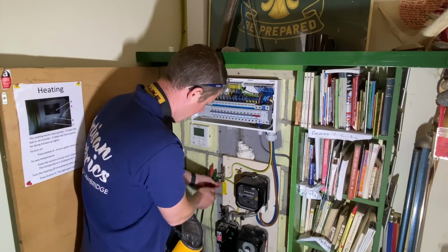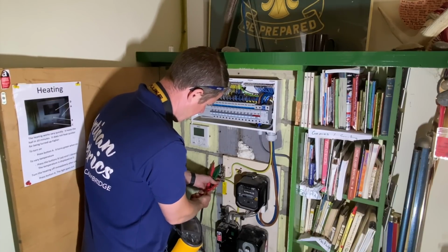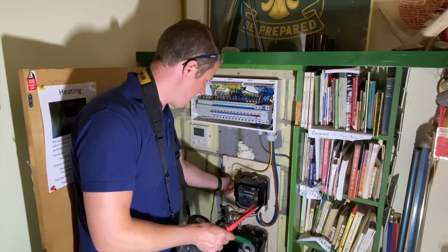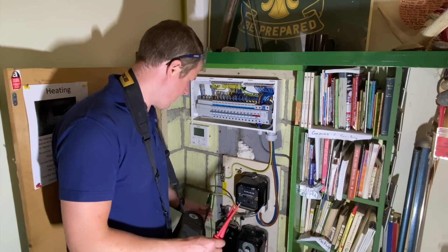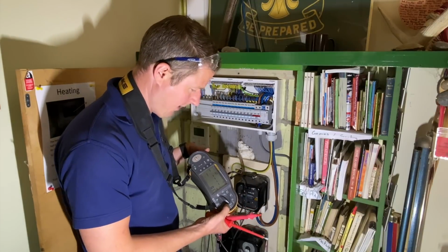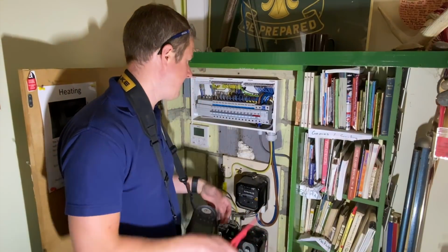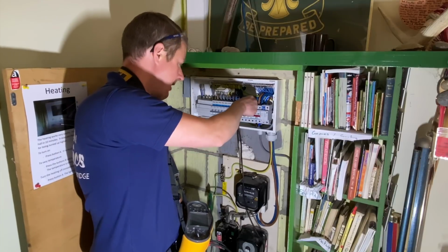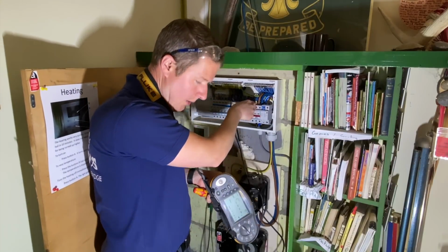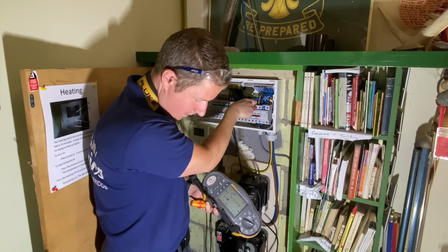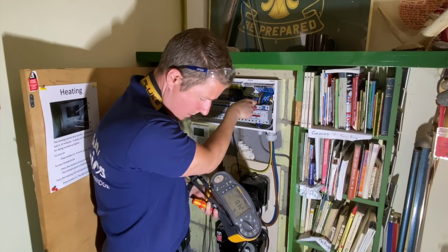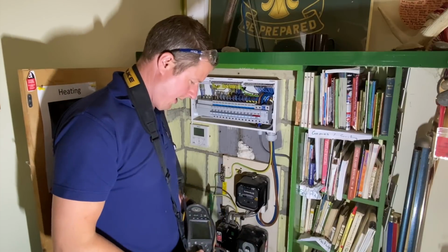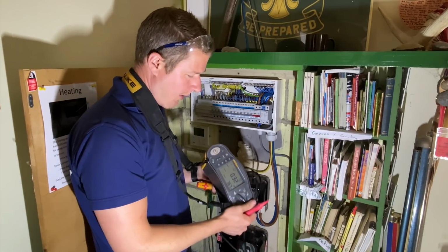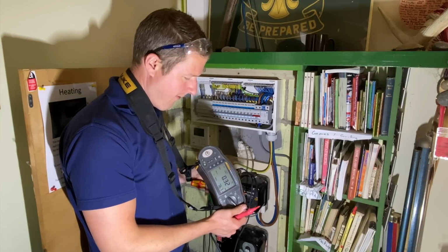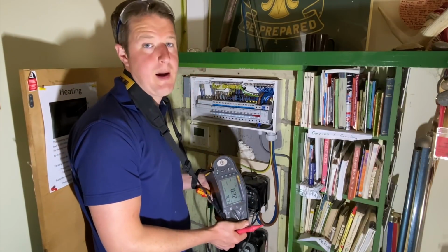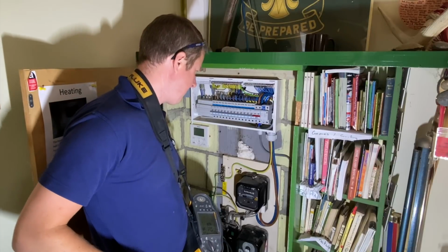So we'll disconnect the main earth here, like so. Put the crocodile clip on there. We have the tester on the earth loop impedance high current setting, which is a 2 lead setting, and then we test from there to the live conductor. And we have 0.32, which is acceptable for this kind of installation. It's close to the limit. It should be 0.35 maximum, so it's just under the maximum required, but that's absolutely fine.